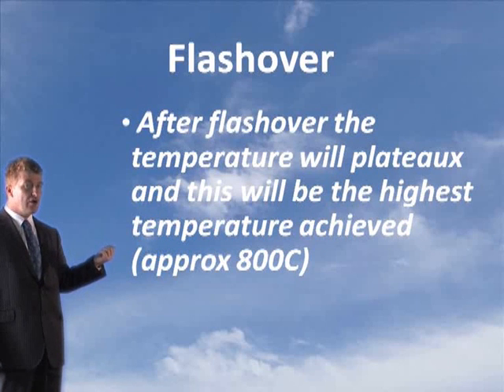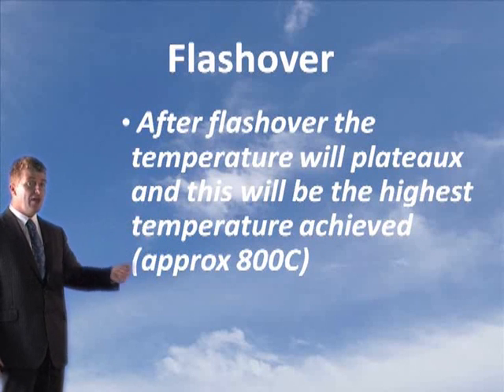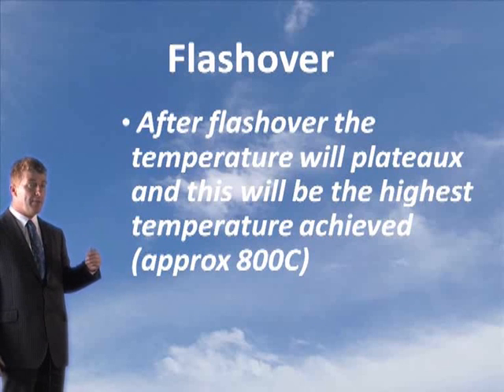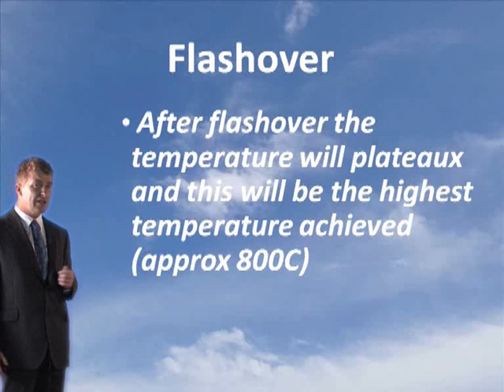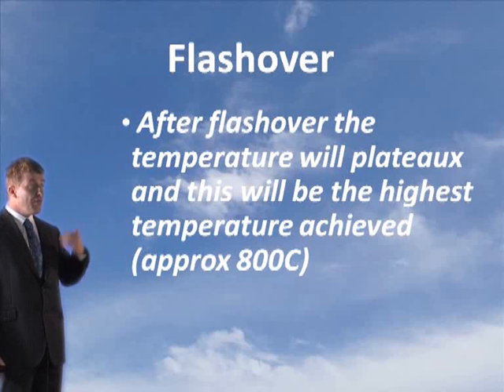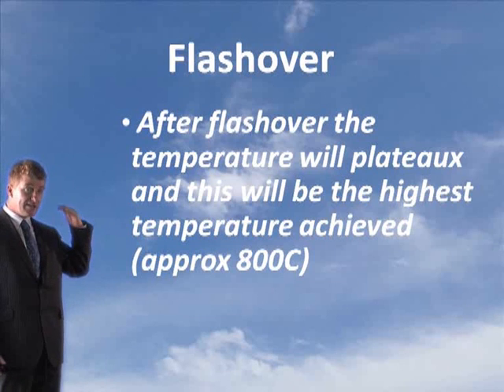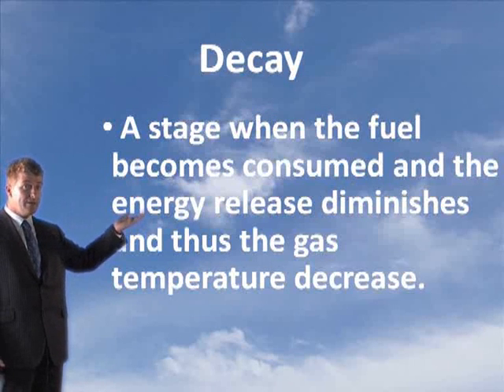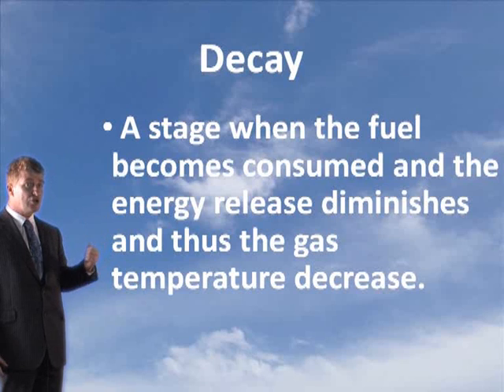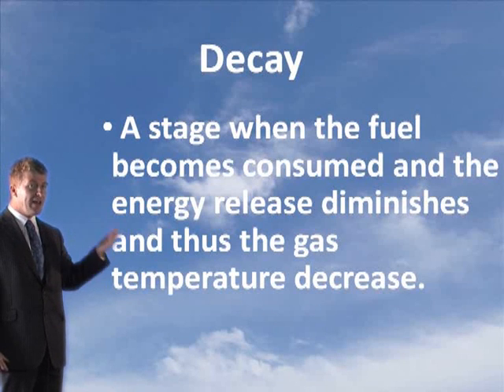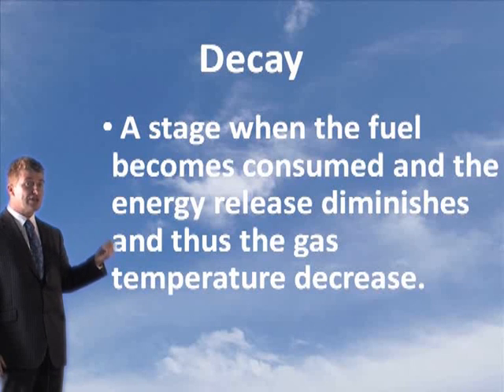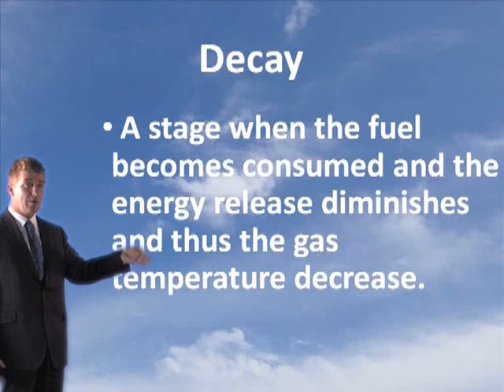After the flashover, the temperature plateaus and this is the highest temperature you're going to get in that compartment — normally about 800 degrees. Then, as the fire starts to decay after this phase, a stage comes when the fuel becomes consumed and the energy release diminishes, and thus the gas temperature will decrease. In other words, the fire will start to go out.